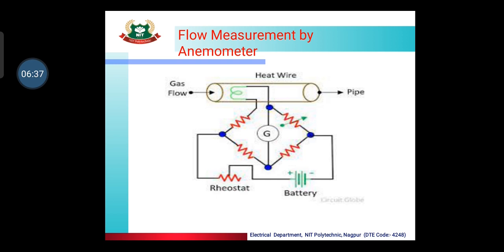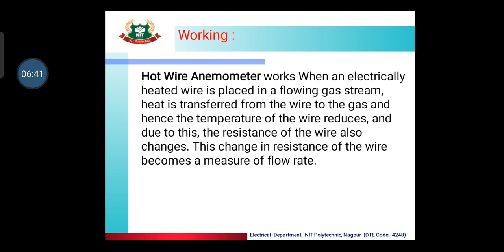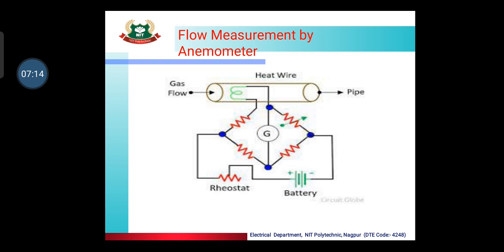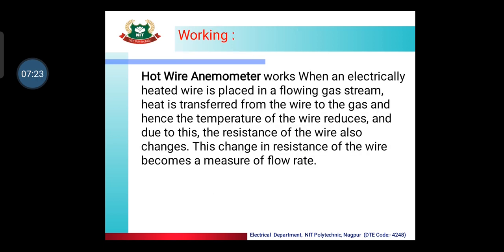The hot wire anemometer works when an electrically heated wire is placed in a flowing gas stream. Heat is transferred from the wire to the gas, and hence the temperature of the wire reduces. Due to this, the resistance of the wire also changes. This change in resistance of the wire becomes a measure of the flow rate. So when heat is transferred from the wire to the gas, the wire temperature decreases, the wire resistance changes, and this change in resistance of the wire becomes a measure of the flow rate.